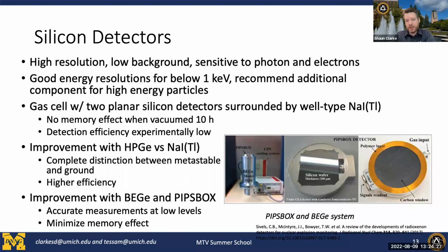which is a good system. Again, it's excellent resolution. The issue is the efficiency. So there's very low efficiency for the silicon wafers, but there's no memory effect. So again, memory effect, as I mentioned before, is this property where the xenon diffuses into the detector material, which is more common for organic detectors. So things like plastic scintillator, which I'll talk about later. Those organic detectors have a much higher propensity to absorb the xenon sample than something like silicon. So no memory effect is good, low efficiency is bad.